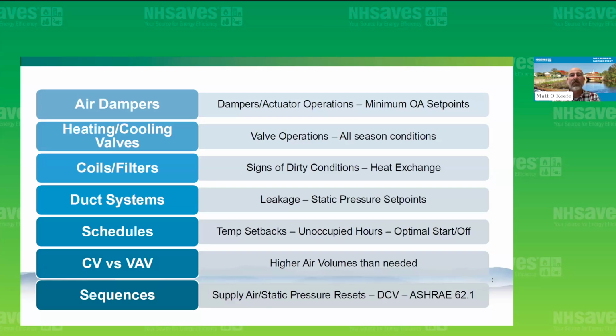So it's running 24/7 or whatever it is, where a simple review of schedules can get you to assist and find some savings there. So areas to improve the existing systems typically come from identifying locations where it was designed one way, but now it can operate more efficiently. So older air handler systems would typically run with a constant volume system, where it might be able to be modified to a VAV system with some downstream components in place or added.